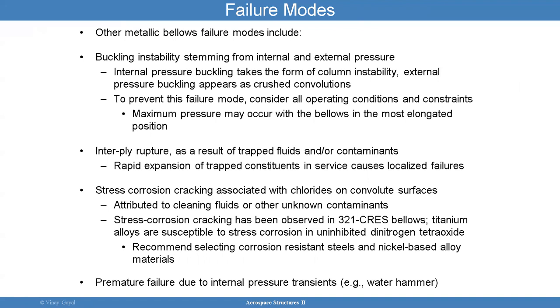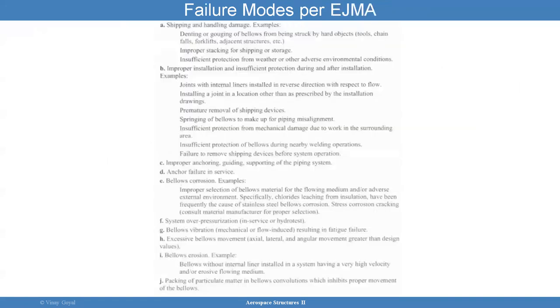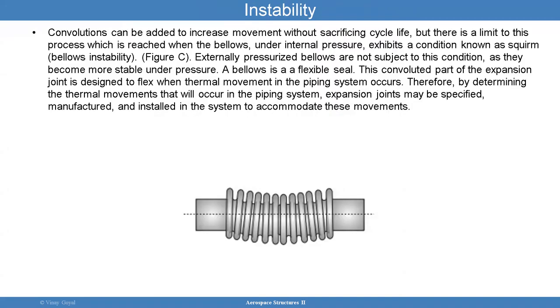Other metallic bellows failure modes include buckling instability, interply rupture if trapped fluid between plies gets heated up, stress corrosion cracking, and premature failure due to internal pressure transients. Failure modes per EJMA include shipping and handling damage, improper installation, improper anchoring, bellows corrosion, system over-pressurization, bellows vibration, excessive bellows movement, bellows erosion, and bellows convolution issues. You can have instability. Convolutions can be added to increase movement without sacrificing life, but there is a limit.